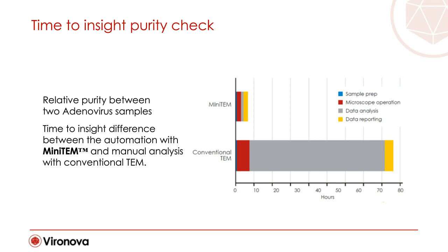The online image analysis takes also about an hour per sample in the MiniTEM, providing about 60,000 registered particles. This is not at all a task that is feasible to perform manually, but extrapolated data shows that it would take about 2 weeks of manual work. So now concluding, the time of analysis with MiniTEM is feasible to use in routine work. So back to you, Josefina.